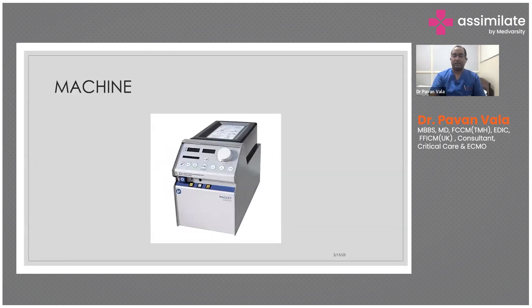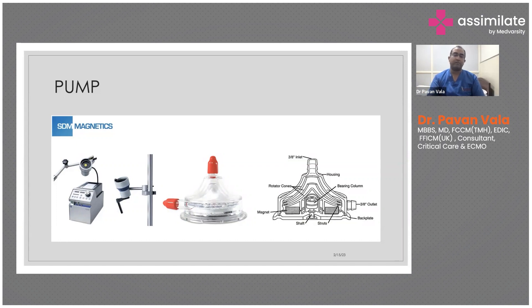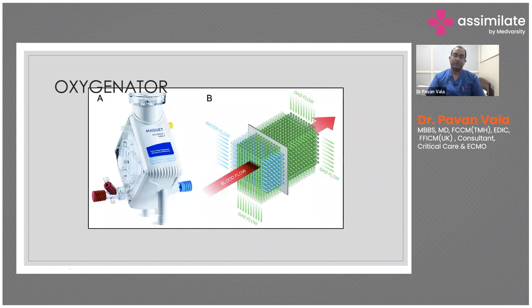This is what a basic Maquet Rotaflow machine looks like — a display and dials in front, and the pump at the back. It uses a centrifugal pump, unlike dialysis machines which use a roller pump. For the flows we target on ECMO — five to six liters per minute — a roller pump would cause too much hemolysis. The centrifugal pump uses a magnet spinning at up to 3,000–4,000 RPM, generating centrifugal force that sucks in blood and pushes it out.